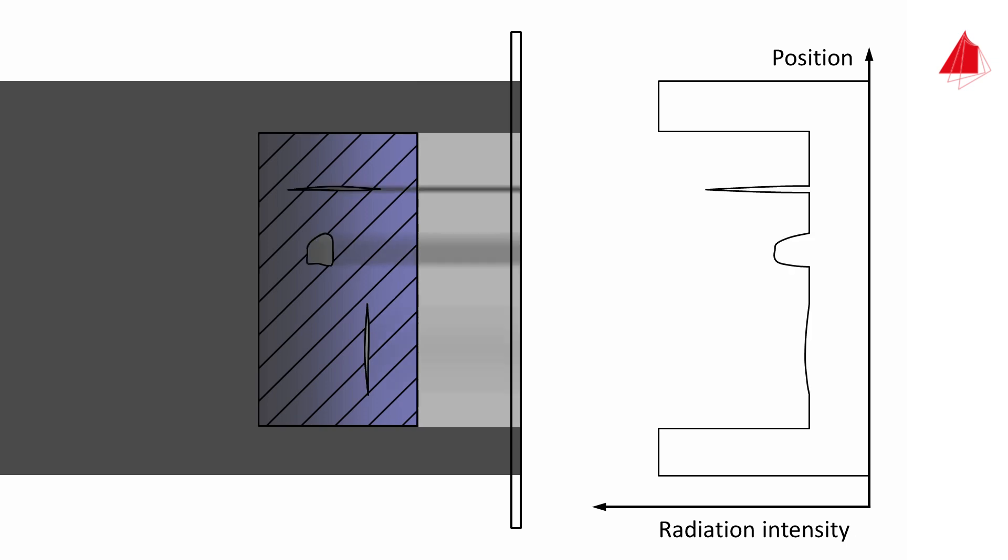Defects such as cracks or pores absorb very little radiation. Therefore, places with defects lead to higher radiation intensity at the image capture unit than flawless places. Defects extended in beam propagation direction can be seen particularly well. Those defects which only have a small spatial extension in beam propagation direction can hardly be seen or cannot be seen at all.